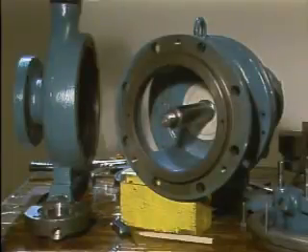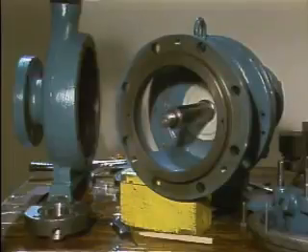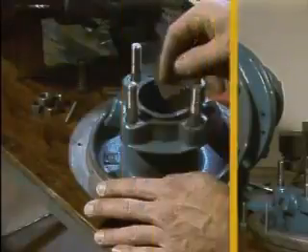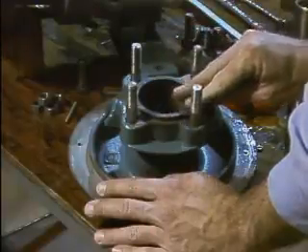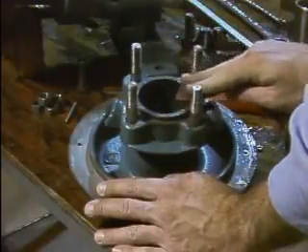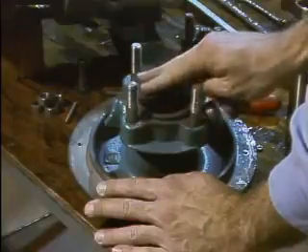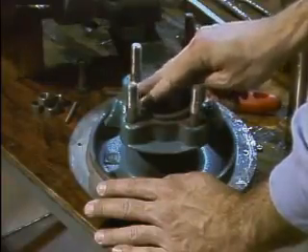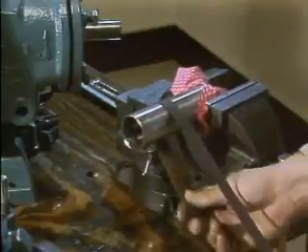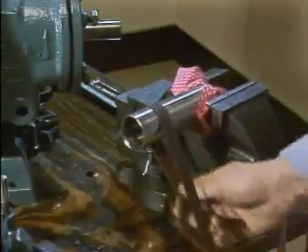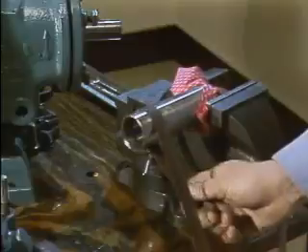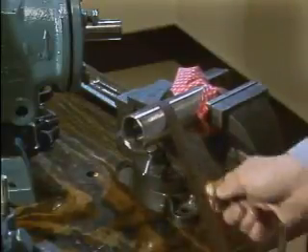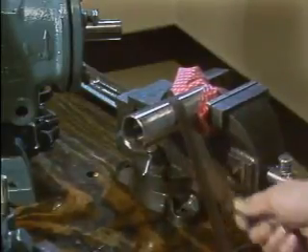After a pump has been disassembled and its damaged mechanical seal has been removed, certain checks and measurements must be made before a new seal is installed. One of the first things to do is to check all machined surfaces for nicks and burrs. Minor imperfections can usually be removed with a light abrasive. Defects on the machined surfaces of the frame, the gland plate, the stuffing box housing, the shaft, or the sleeve could result in leaks and damaged components.